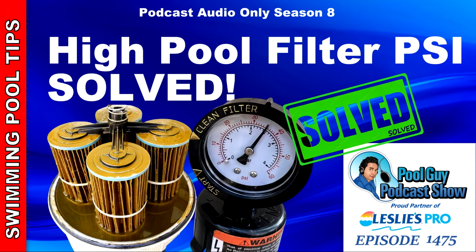Now, what actually is the starting PSI of a filter? It's really hard to say because of the variable speed pumps. At a lower RPM, the PSI is going to be lower. At a higher RPM, it's going to be higher. If you're in spa mode, it's going to be higher automatically because the spa jets are smaller. So it's really hard to say what is a good starting PSI. I guess the best way to find out is to turn your VS pump, variable speed pump, to 100% output or full speed, or 3450 RPMs, and then see what the gauge is at.